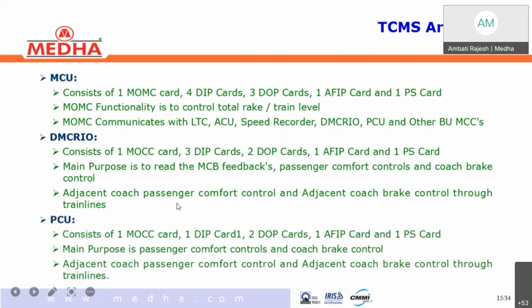Similarly, the PCU, passenger comfort unit, only the nomenclature is different. In the DMC coach, we call it DMC RIO. In all other coaches, we call it PCU, passenger comfort unit. The same hardware again: one control card, one digital input card, two digital output cards, one analog input frequency input card, and one power supply card. Only the software logics differ from other computers. And the main purpose of this passenger comfort unit also is passenger comfort controls and coach brake control of its own coach as well as adjacent coach passenger comfort. In case of failure of the passenger comfort unit in the DMC coach, the adjacent trailer coach can provide the supply to DMC coach passenger comforts and brake controls via train line signals.